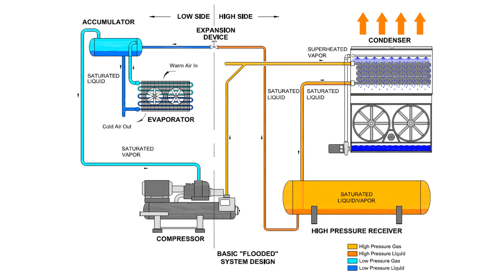The purpose of a high pressure receiver is to provide a safe location to add and store high pressure liquid ammonia in a refrigeration system. Typically, the high pressure receiver receives high pressure liquid from the condensers and supplies high pressure liquid to each zone of refrigeration and recirculator. The high pressure receiver is also used to provide storage for ammonia not being used in the system at any given moment. Under normal conditions, the high pressure receiver contains high pressure liquid and vapor ammonia.